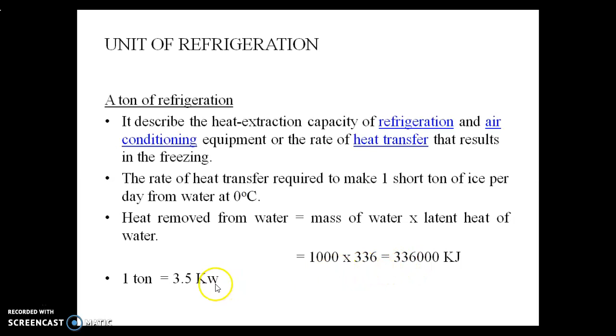The amount of heat removed from water is equal to mass of water times latent heat of the water. Mass of water 1000 kilogram, latent heat of the water 336 kilojoule per kilogram. Totally 336,000 kilojoule amount of heat must be removed from water to transfer into solid phase in 24 hours. We divide this value by 24 hours and we get 1 ton equal to 3.5 kilowatt.